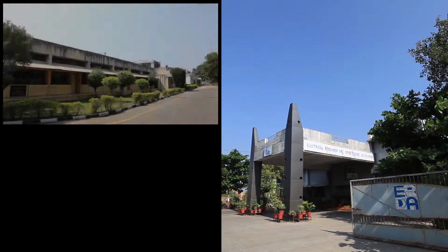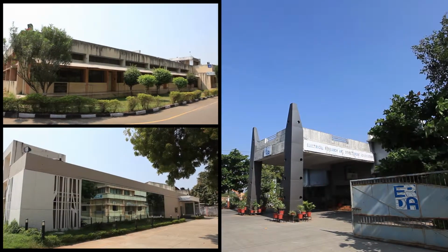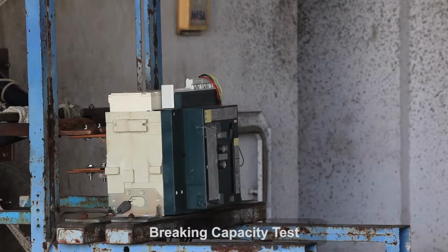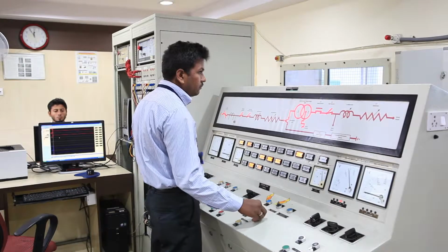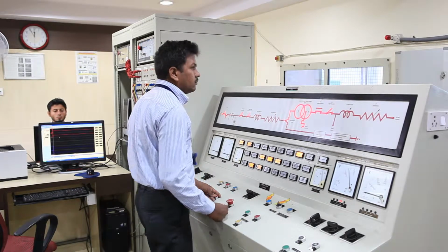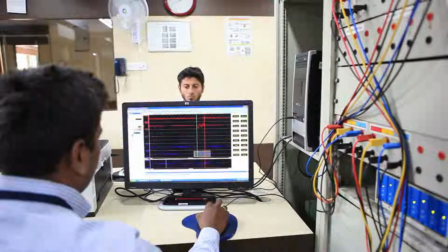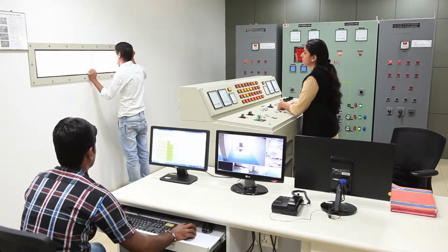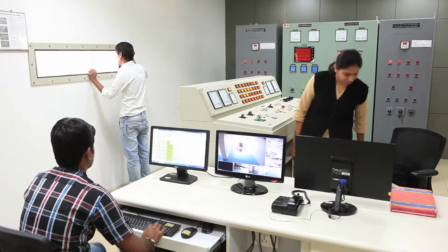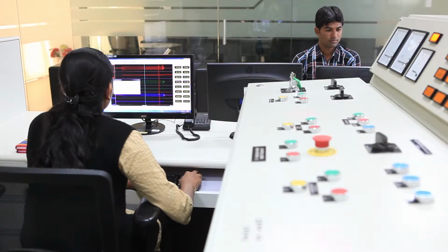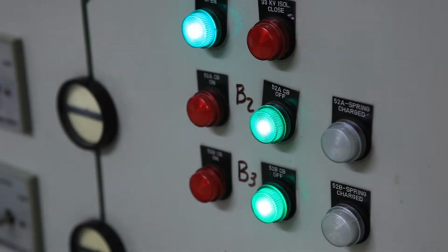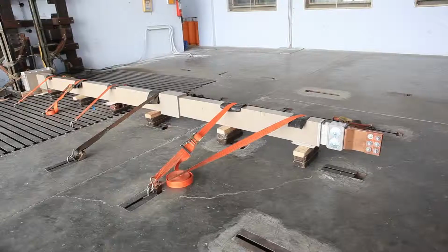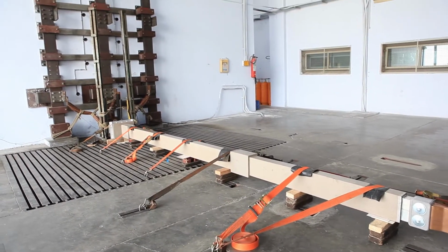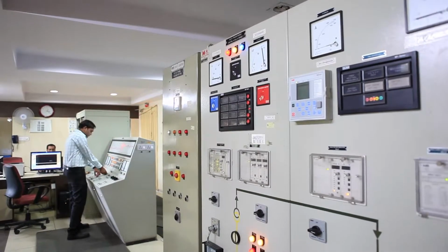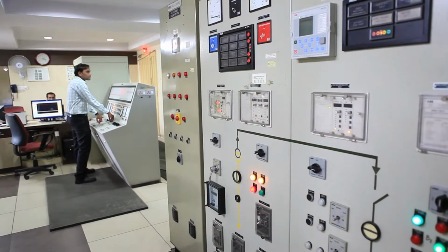ERDA has 3 modern low voltage short circuit test stations to test switchgear products. The Savli laboratory has a short circuit capacity of 120 kiloamperes for 1 second at 575 volts. And the laboratories at Makarpura have a capacity of 50 kiloamperes for 1 second at 525 volts. We test switchgear products for short time withstand test, conditional short circuit test, and short circuit making and breaking capacity tests.